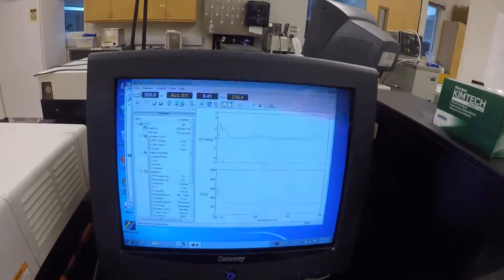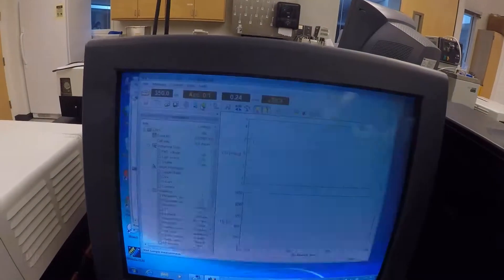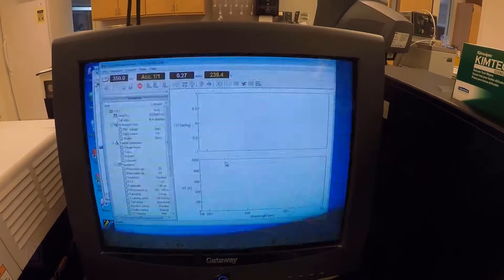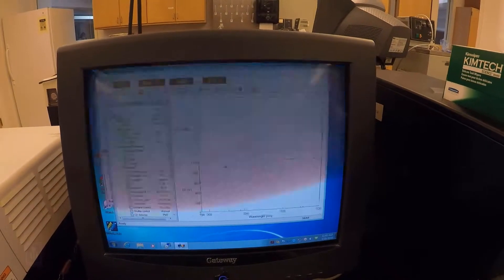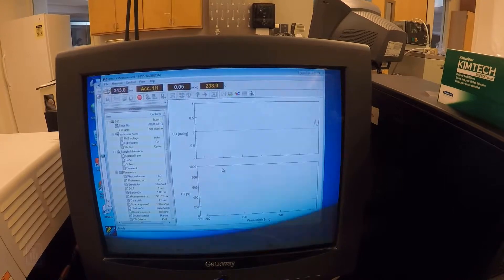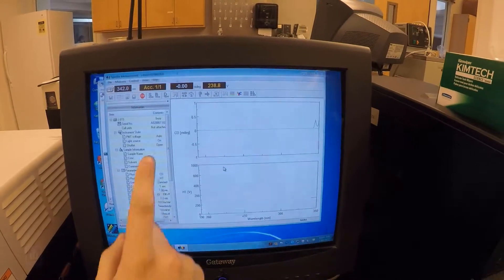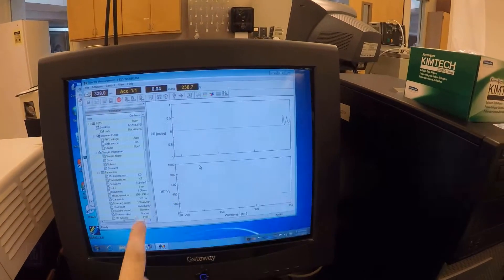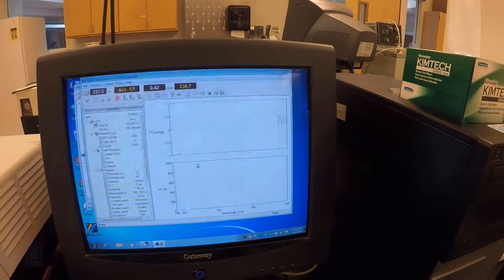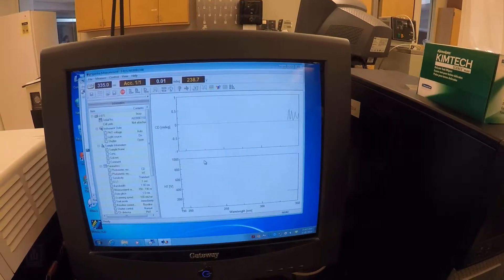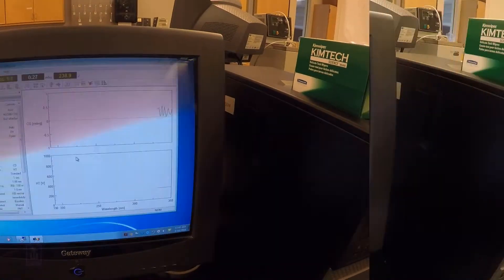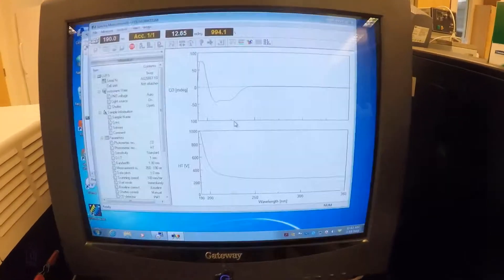Instead of the B this time, we're going to use the S, which is our sample measurement. And all you have to do is hit OK. And we're going to let that go ahead and scan through the whole spectrum. Again, it starts here at a low axis, and it will scale as the peaks start to appear. So we'll just watch that happen.